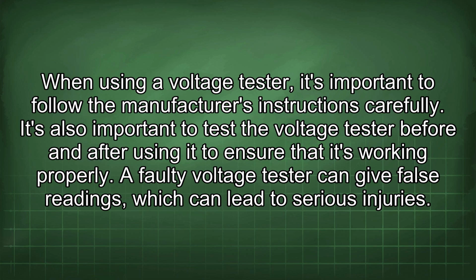When using a voltage tester, it's important to follow the manufacturer's instructions carefully. It's also important to test the voltage tester before and after using it to ensure that it's working properly. A faulty voltage tester can give false readings, which can lead to serious injuries.